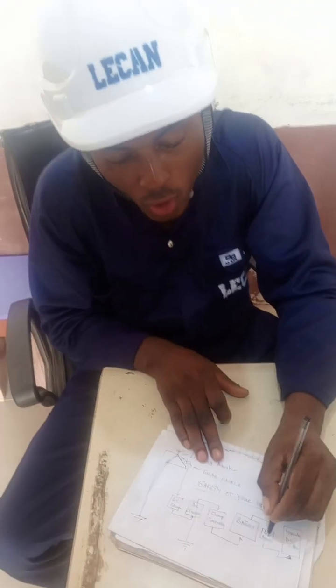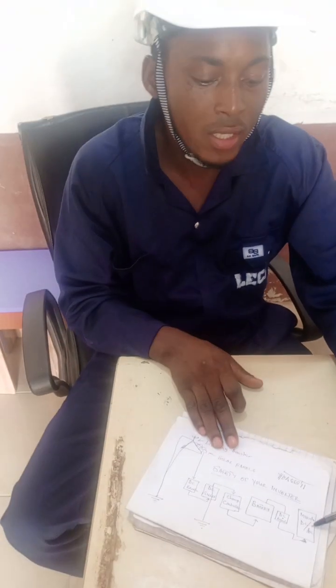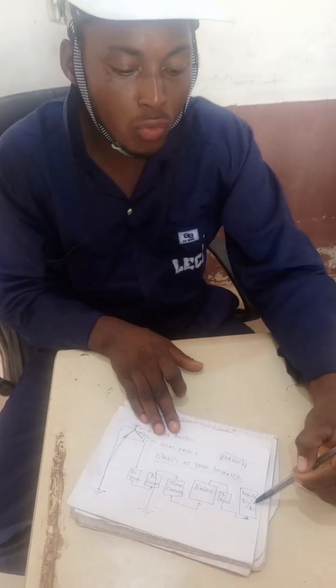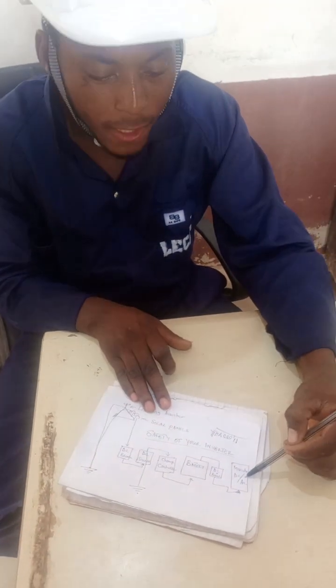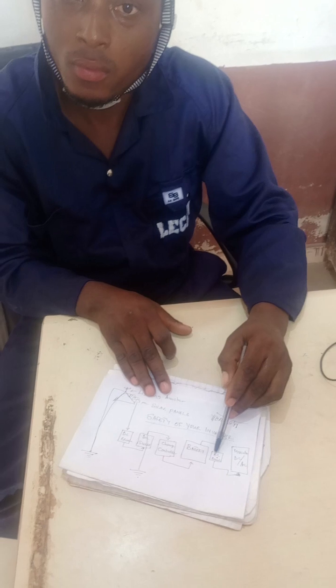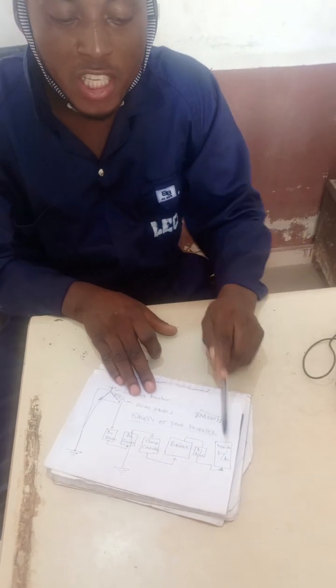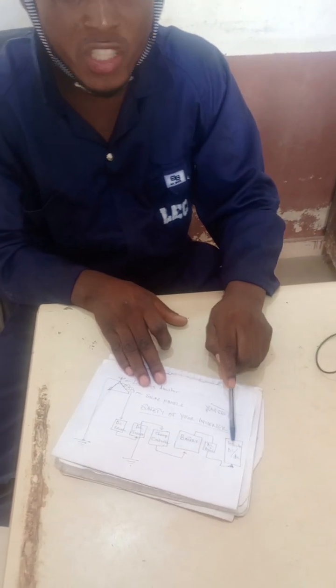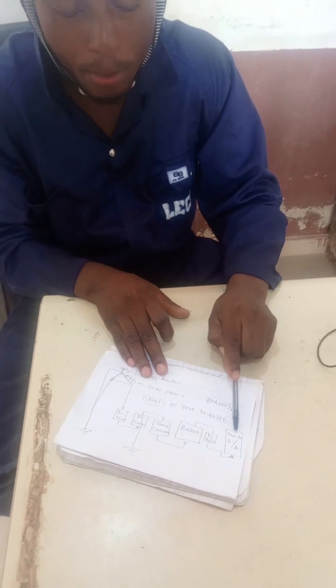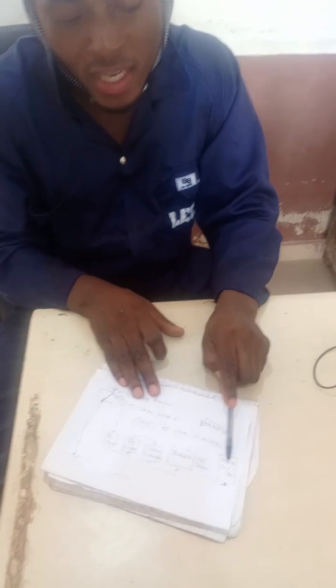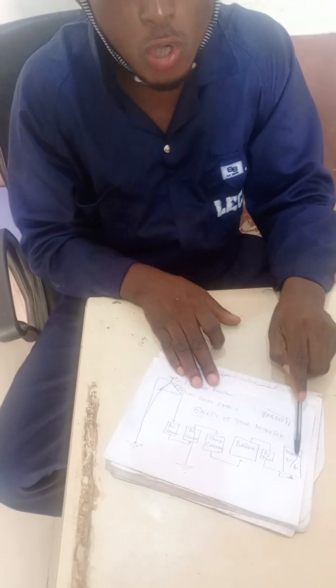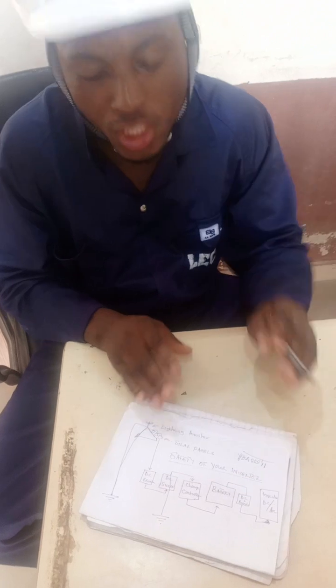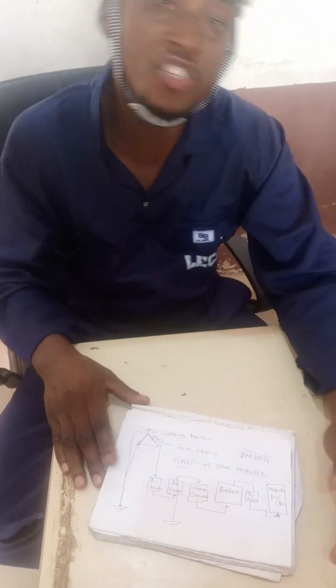So this breaker will sense excess current being drained, it will trip off. So the moment this inverter, if it's meant to draw 100 amps from the battery, the moment there's a short circuit on this inverter, it will draw more than 100 amps. Therefore, your battery will become safe, because the breaker here will trip to keep your battery very safe.